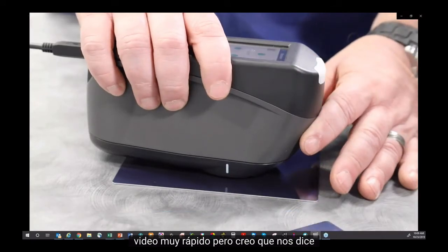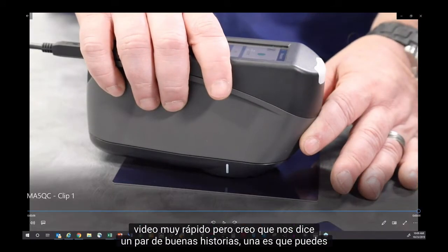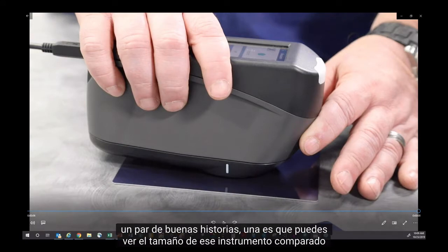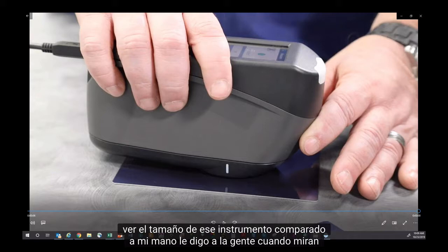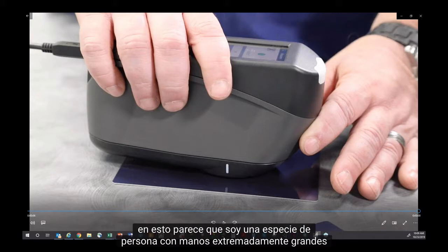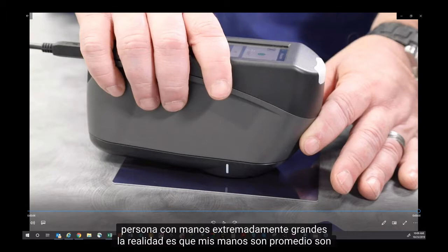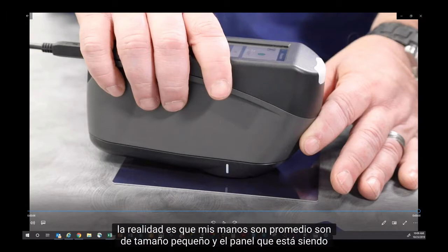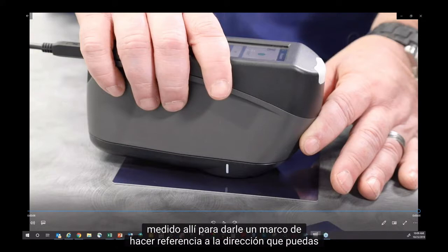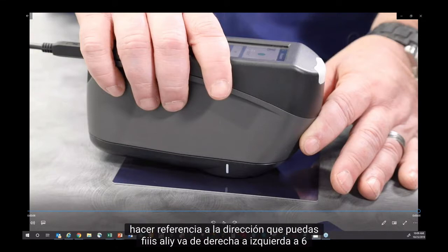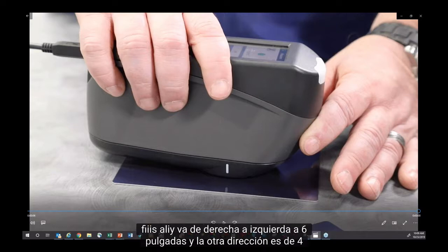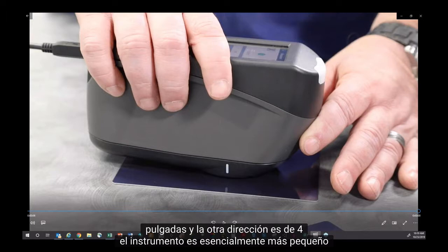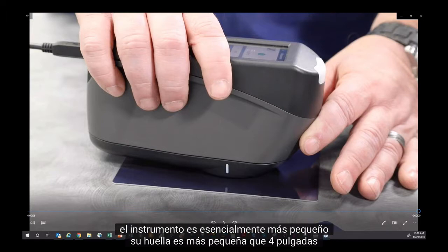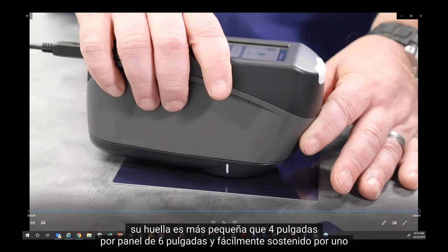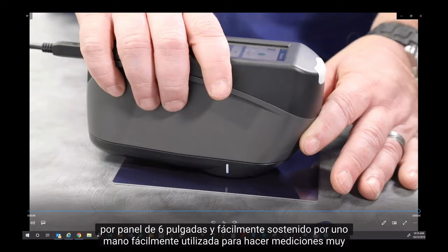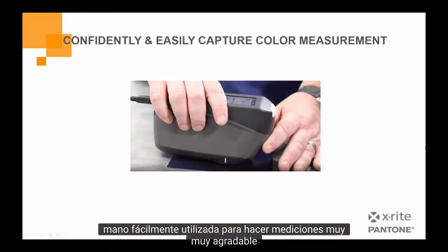It's a very quick video, but I think it tells us a couple of good stories. One is, you can see the size of that instrument compared to my hands. I tell people when they look at this, it looks like I'm some kind of person with extremely large hands. The reality is that my hands are average or small in size. And the panel that's being measured there, to give you a frame of reference, the direction that you can see easily going from right to left is 6 inches. And the other direction is 4. So the instrument's footprint is smaller than a 4-inch by 6-inch panel, and easily held by one hand, easily used to do measurements very, very nicely.